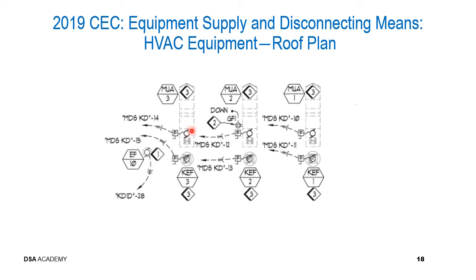Now, as you can see, looking at, let's say, MUA number 1, this little symbol right here with an F in a box, this is the symbol for a fused disconnect. As we've been discussing, this disconnect is required on all air handler units roof mounted, and also generally on all exhaust fans. Now, there's additional information that we should touch on here. If you look at this arrow, this signifies a home run for this particular fused disconnect, which is the disconnect supplying the fan motor inside this air handler unit. This home run is shown going back to panel MDS-KD, circuit number 10.